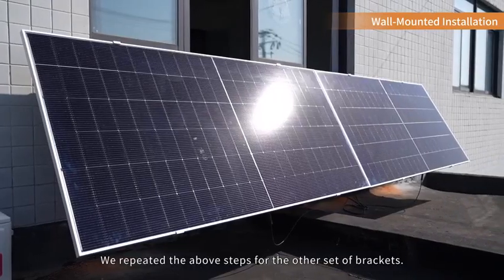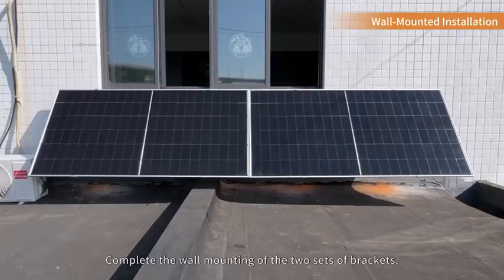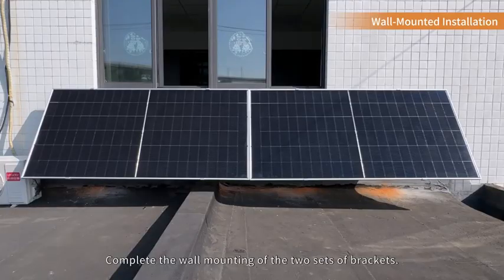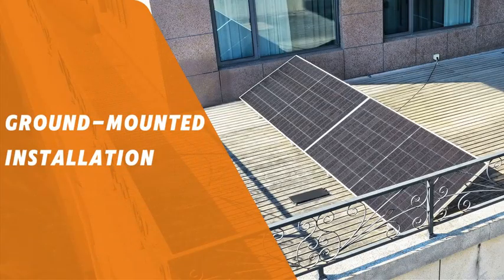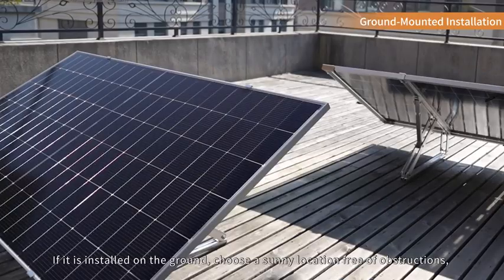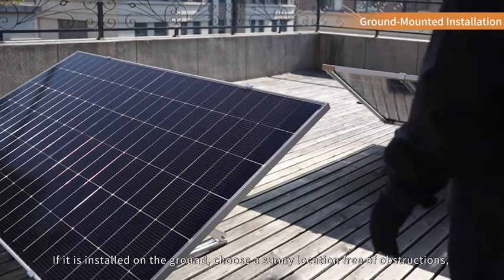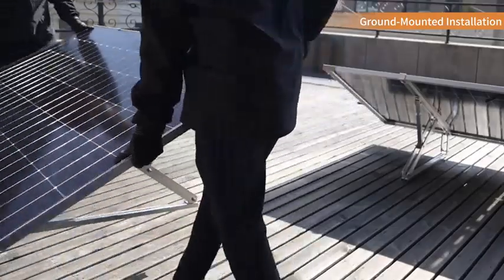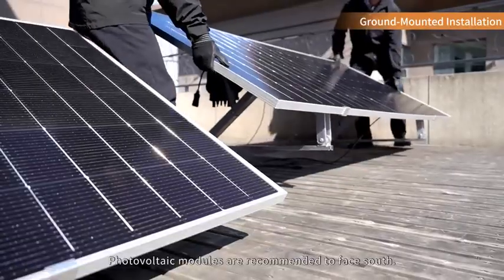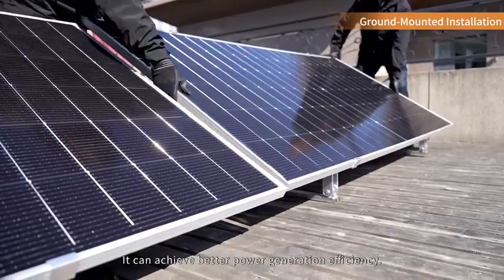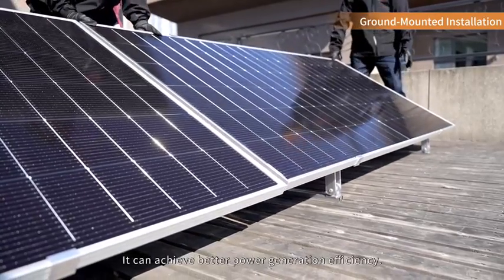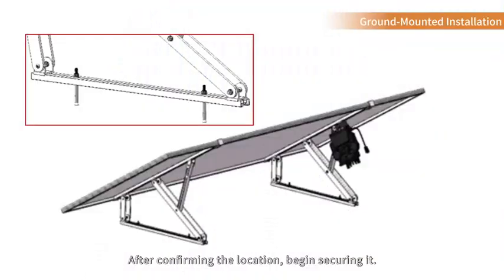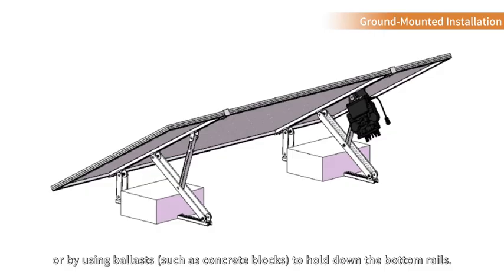We repeat the above steps for the other set of brackets. Complete the wall mounting of the two sets of brackets. If it is installed on the ground, choose a sunny location free of obstructions. Photovoltaic modules are recommended to face south. It can achieve better power generation efficiency. After confirming the location, begin securing it. Secure using M8X100 expansion bolts or by using ballasts such as concrete blocks to hold down the bottom rails.